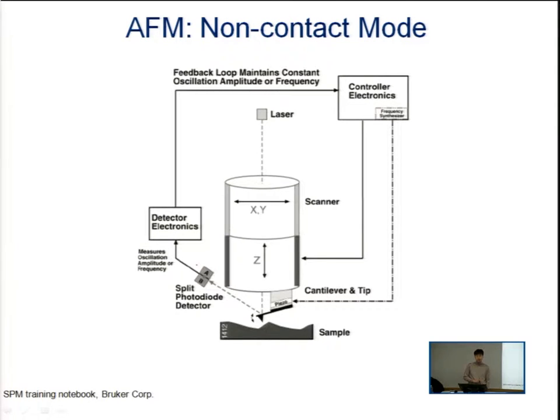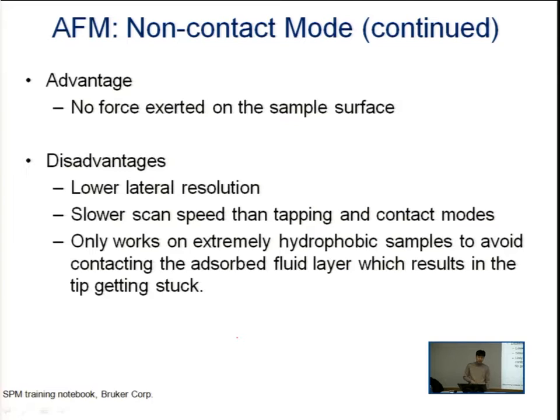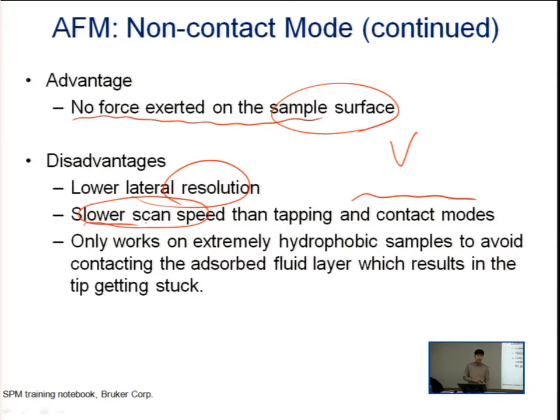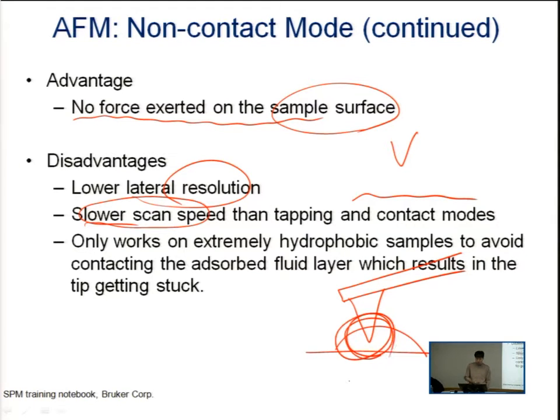The non-contact mode is similar to tapping mode but has a much bigger gap between the cantilever and the surface. It has all the advantages of tapping mode and, since it never touches the surface, does not damage anything. However, as the distance between tip and surface increases, resolution decreases. It also has the slowest scan speed. Additionally, if there is moisture present on the sample surface, the cantilever can become stuck by the moisture — another disadvantage of this mode.